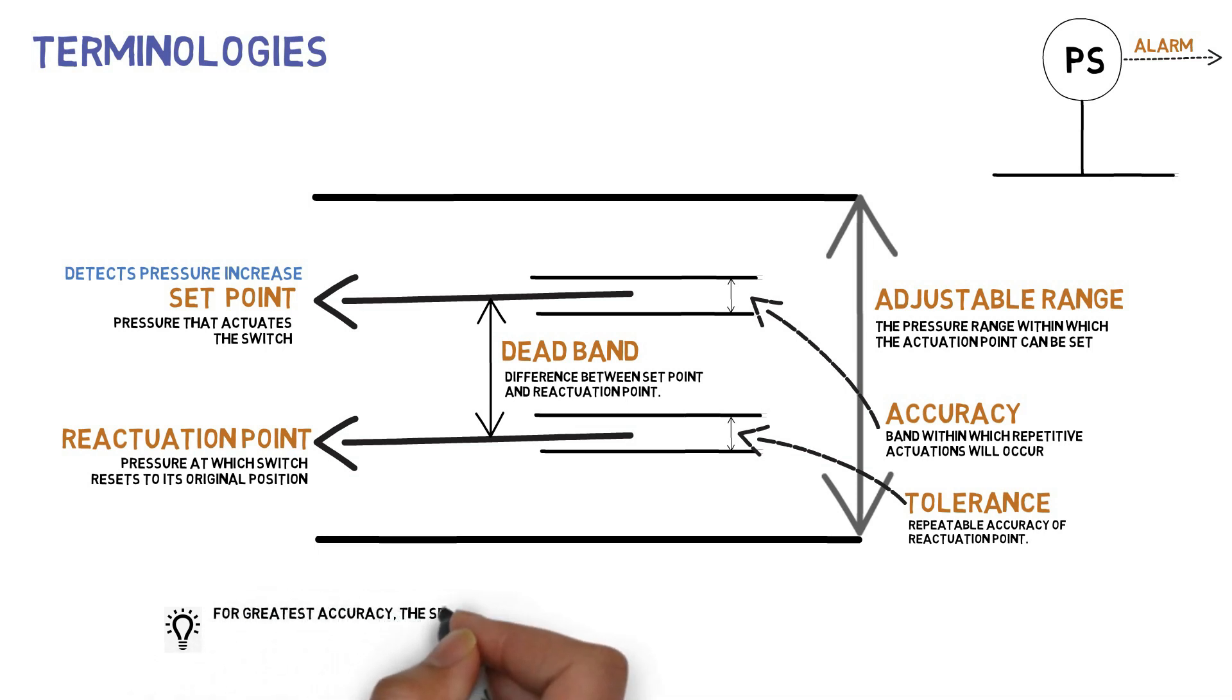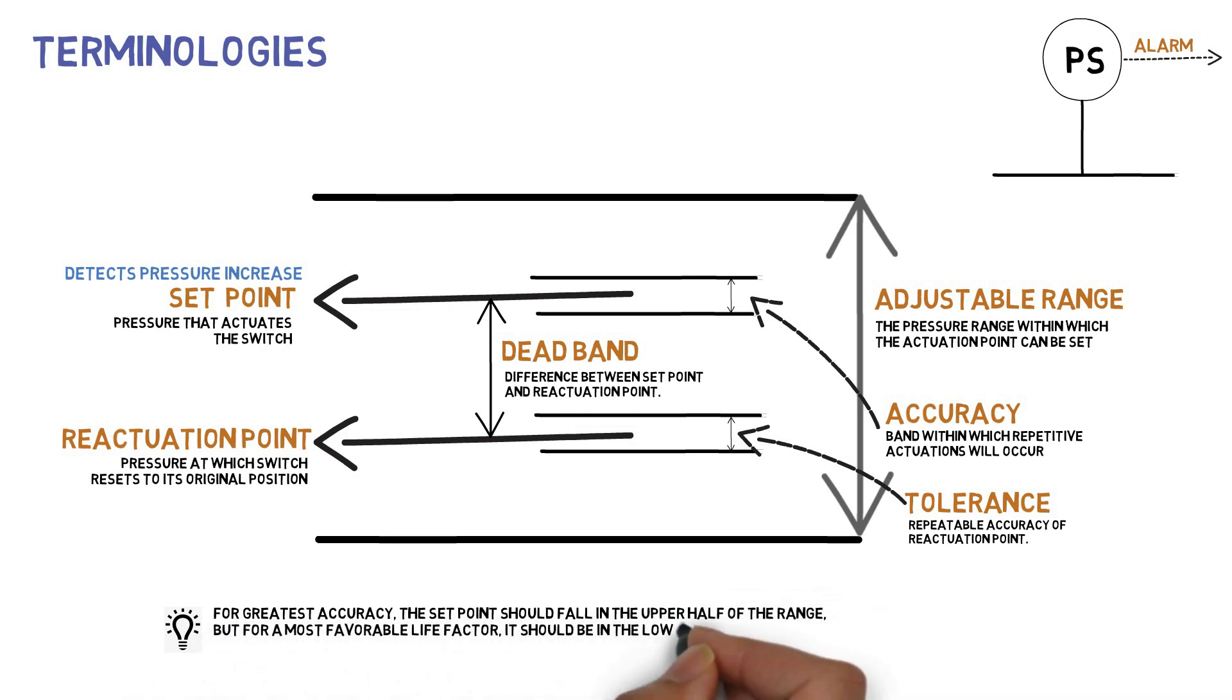For greatest accuracy, the set point should fall in the upper half of the range, but for most favorable life factor, it should be in the lower half. The usually acceptable compromise is to locate the set point in the middle third of the range.